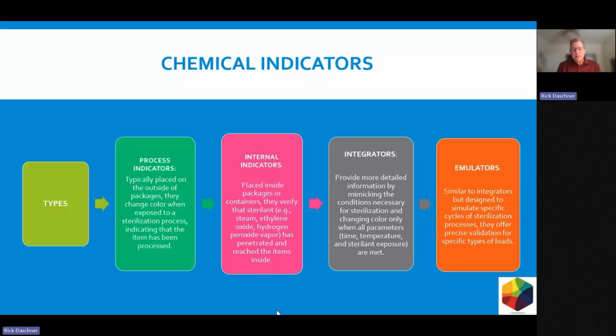Internal indicators. Now, these are going to be placed within containers to ensure that the sterilization process did make it into, let's say, the inside of a package. They're placed inside packages or containers. They verify that the sterilization agent, steam, ethylene oxide, or hydrogen peroxide, has penetrated or reached the items inside. Again, it gives additional confidence that the sterilization process had reached the product that you're trying to sterilize. And we'll go into why in some of these questions, there were some good questions that we have answers for, on how that might work to give the confidence that the sterilization process was validated.